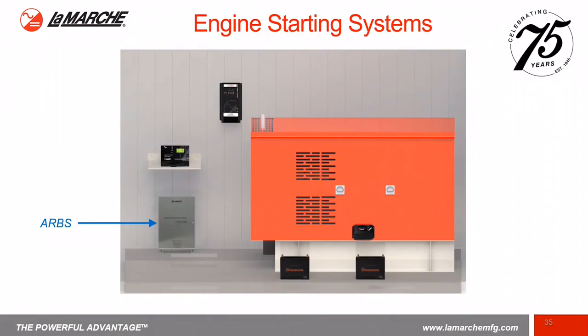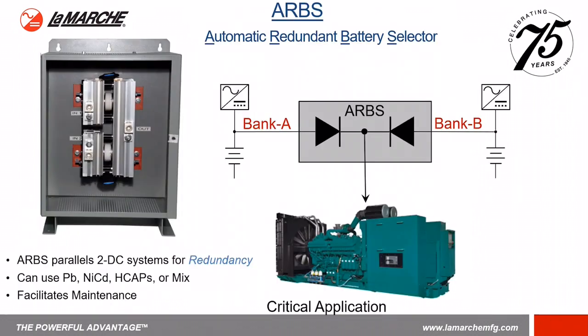We'll talk about some other complementary products. HCAPs currently are not recognized by NFPA 110. And for that, we can provide an ARBS solution where you can go ahead and install your lead acid or NiCad batteries in parallel with the HCAPs. And basically, ARBS is the automatic redundant battery selector and would select between source A or source B to provide the proper current to the generator starting.